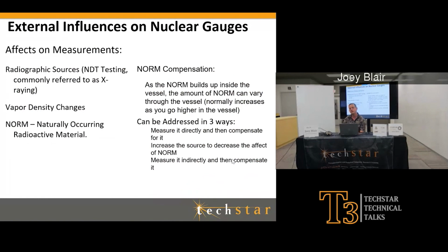So let's think of different things that could be causing it to read 15, 30, or even 50 or 60%. If not as much radiation is coming across the vessel as normal, then I'm going to read a higher level, correct? So one scenario is: let's say I have an agitator blade in there, and now as I've come down, my agitator blade has stopped and it's blocking some of the radiation. That's going to make it read inaccurately - that might make it read 30% or whatever it may read. Let's say I had Dowtherm that was very hot, on the outside as a shield, using it as a cooling element or whatever they're using it for. Well, it's going to have a lower density at warm temperatures and a higher density at cooler temperatures.